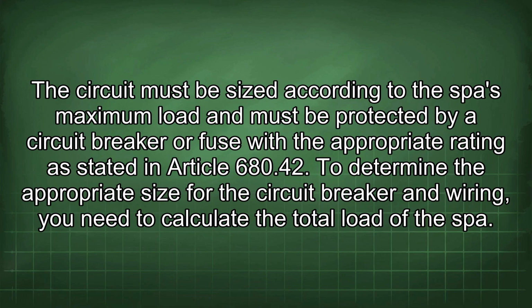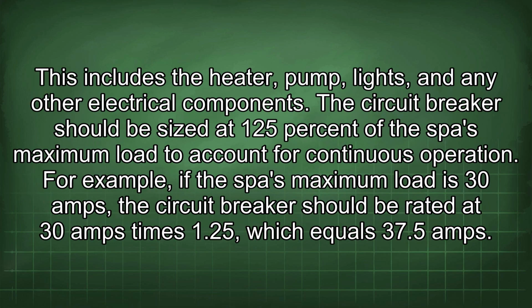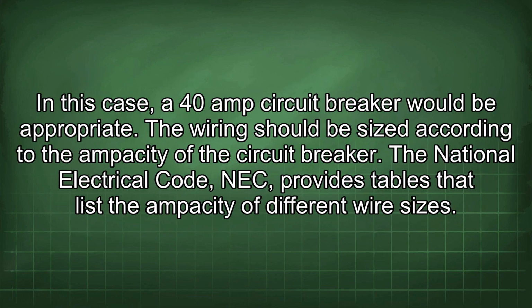The circuit must be sized according to the spa's maximum load and must be protected by a circuit breaker or fuse with the appropriate rating as stated in Article 680.42. To determine the appropriate size for the circuit breaker and wiring, you need to calculate the total load of the spa. This includes the heater, pump, lights, and any other electrical components. The circuit breaker should be sized at 125% of the spa's maximum load to account for continuous operation. For example, if the spa's maximum load is 30 amps, the circuit breaker should be rated at 30 amps times 1.25, which equals 37.5 amps. In this case, a 40 amp circuit breaker would be appropriate.